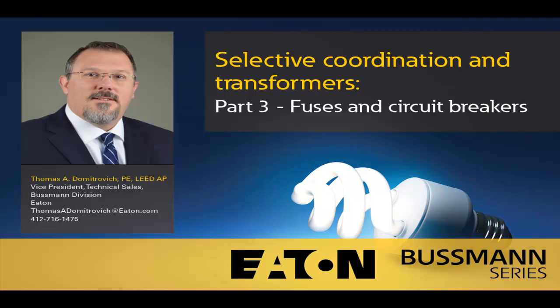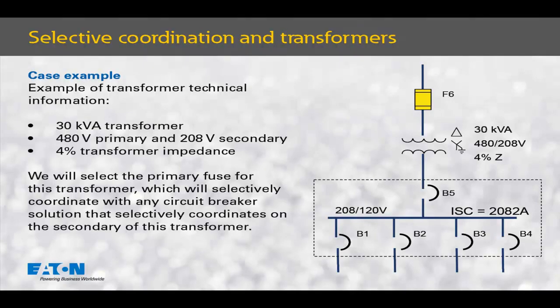Hello, my name is Thomas Dmitrovich. During this session, we'll speak to leveraging fuses and circuit breakers when selectively coordinating around a transformer. The example we'll use is a 30 kVA transformer with a 480 volt line-to-line primary voltage and a 208 volt line-to-line secondary voltage. We are only going to select the primary fuse for this application. This solution will work with any downstream circuit breaker panel solution that selectively coordinates to the maximum available short circuit current on the secondary of this transformer.